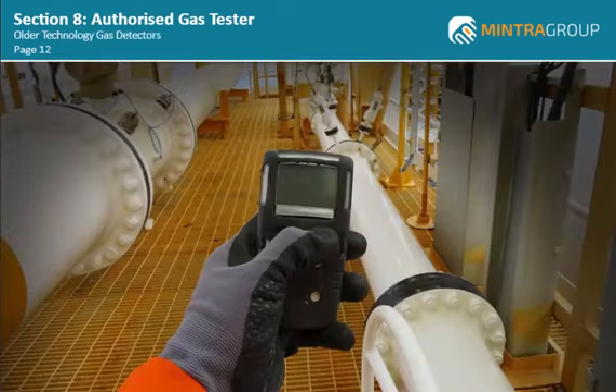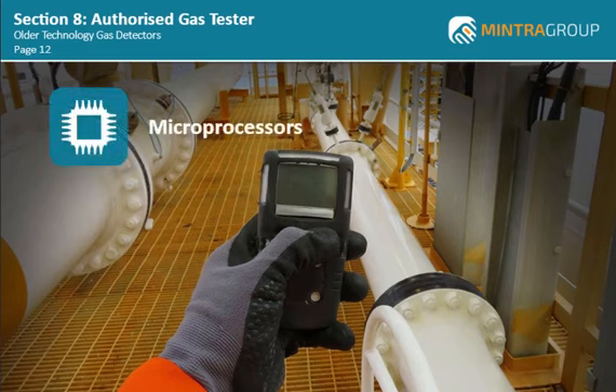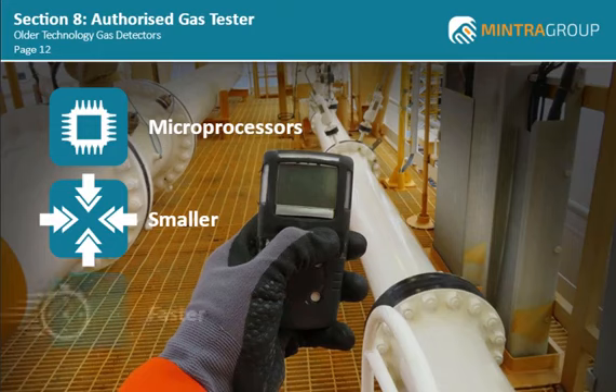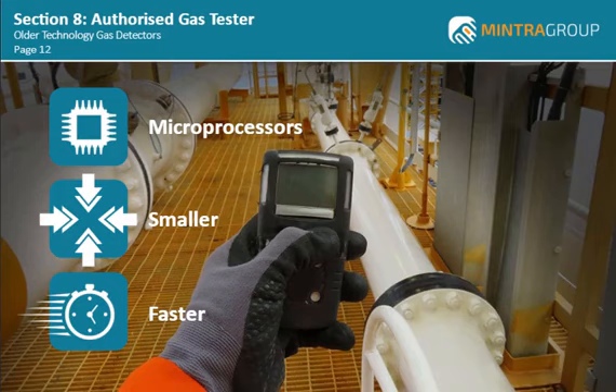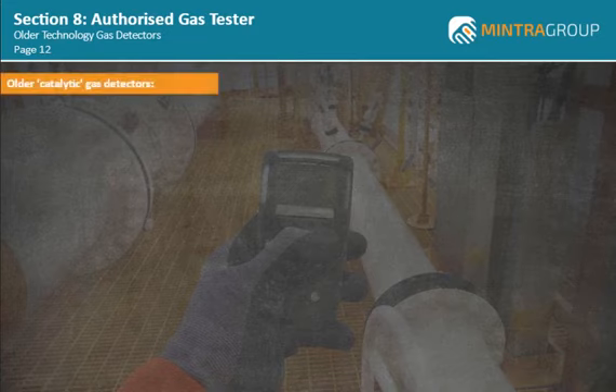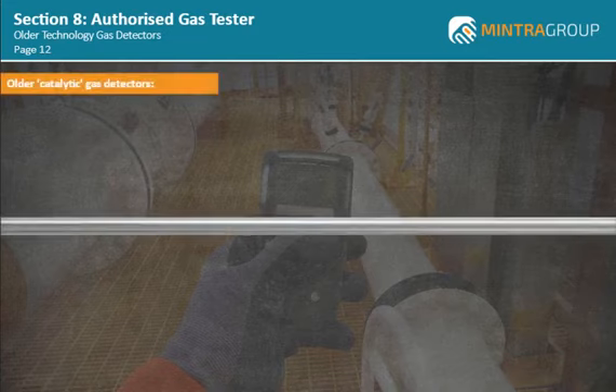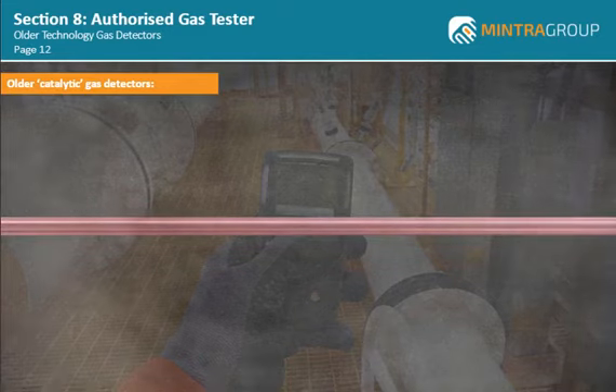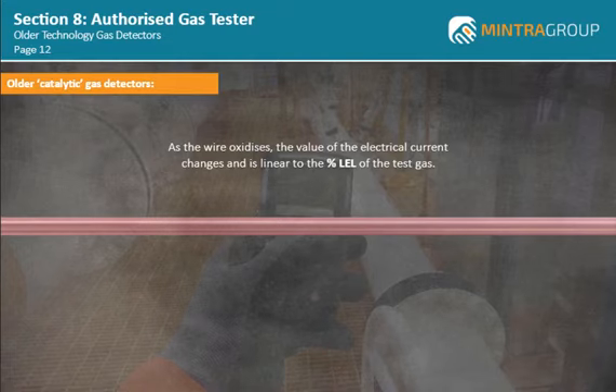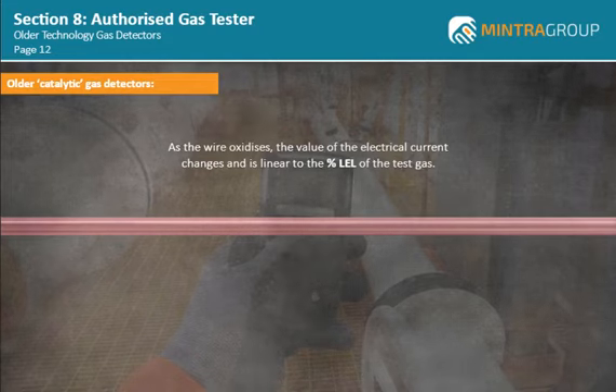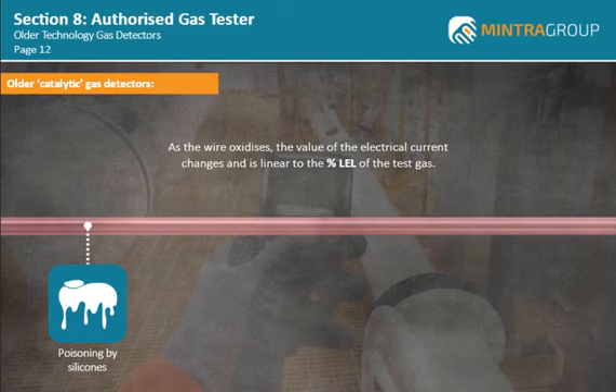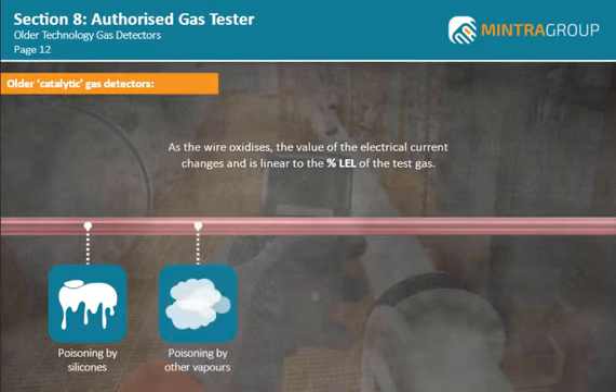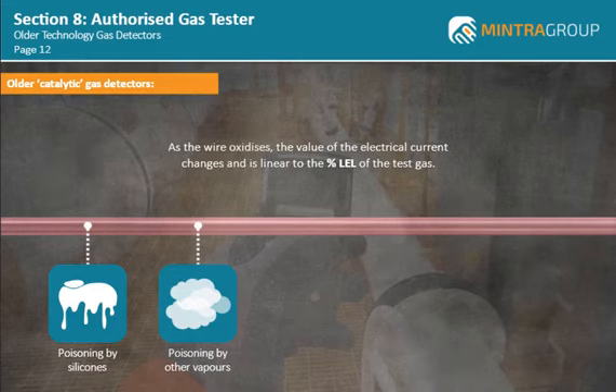Over recent years, gas detector technology has made major advances, with microprocessors being incorporated, components becoming smaller, and the ability to perform faster and more reliable than older models. However, you should be aware that some sites may still have older gas detectors in use. In the older catalytic gas detectors, a platinum wire is heated and the sample gas is passed over this. As the wire oxidizes, the value of the electrical current changes and is linear to the percentage LEL of the test gas. However, this type of system is susceptible to poisoning by silicones and other vapors, which can prevent the correct oxidization and true values of the percentage LEL.